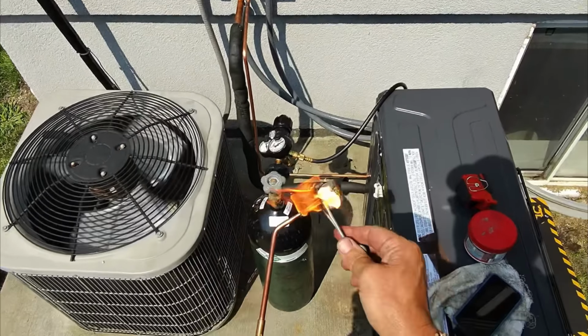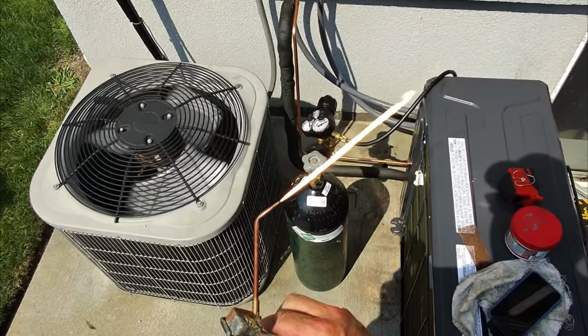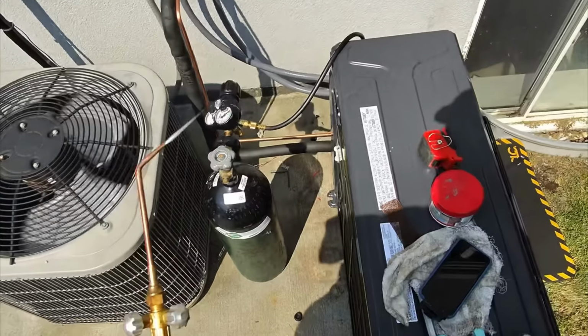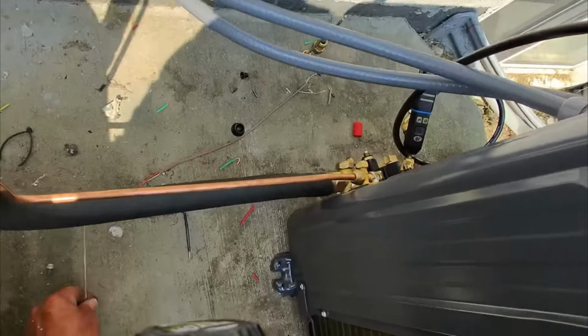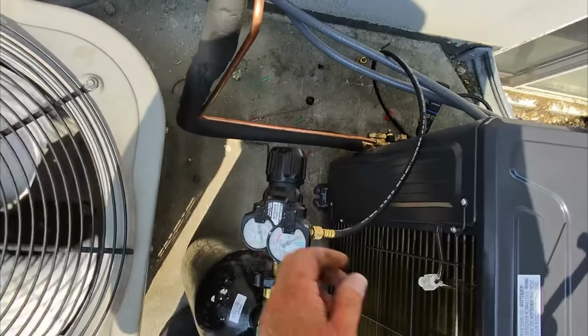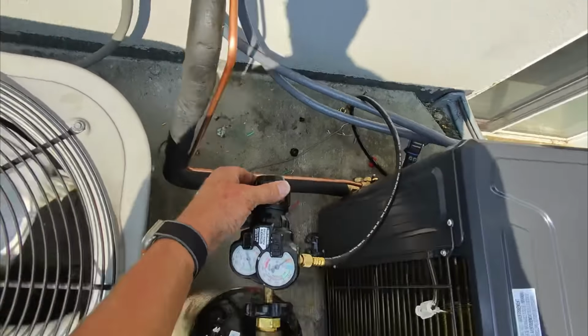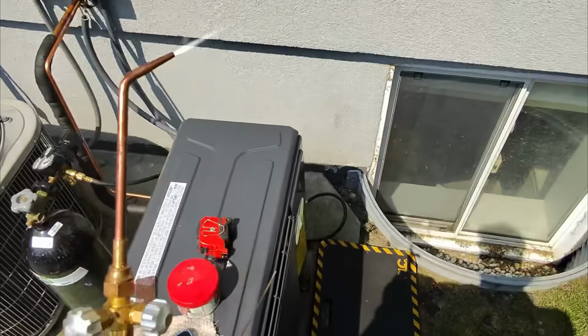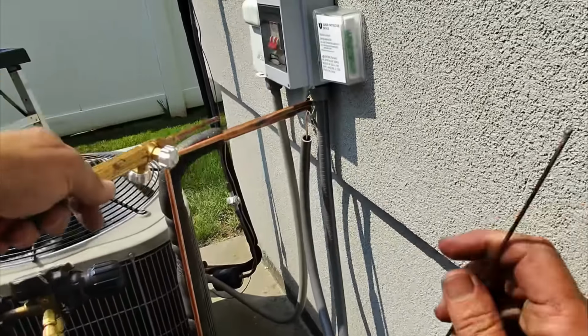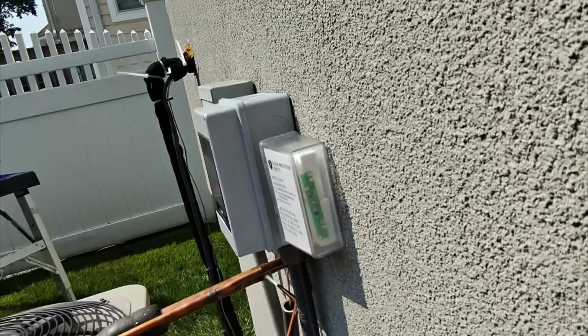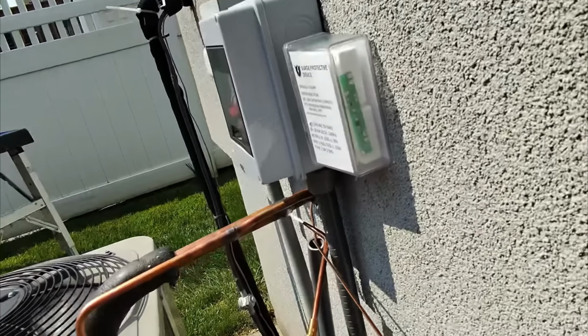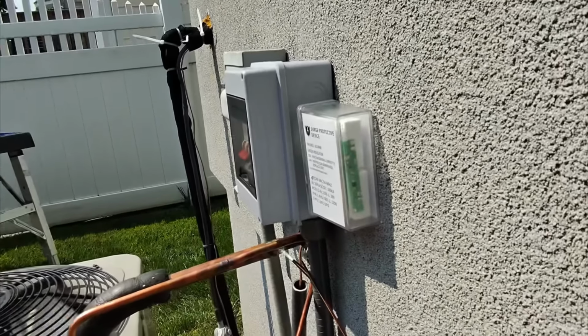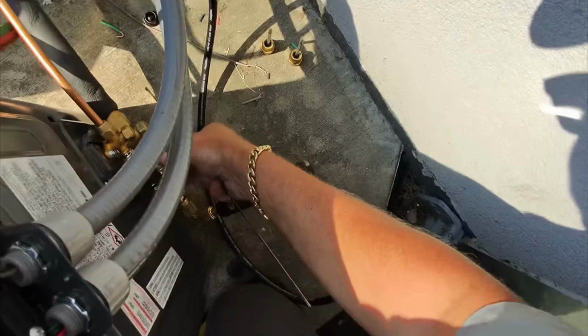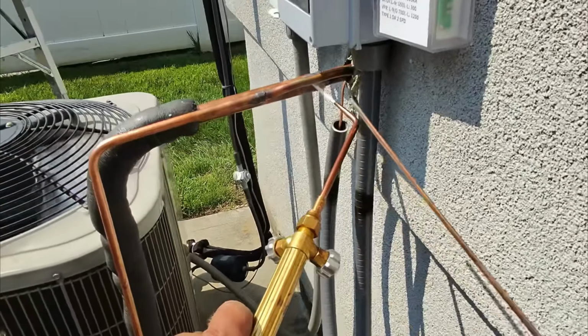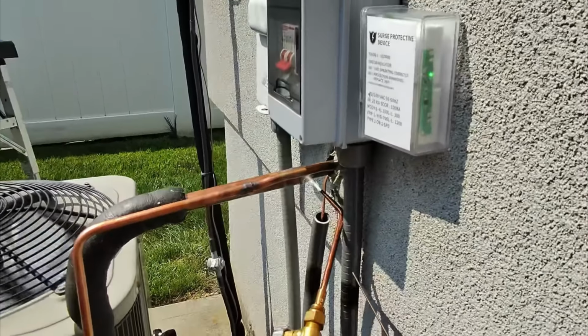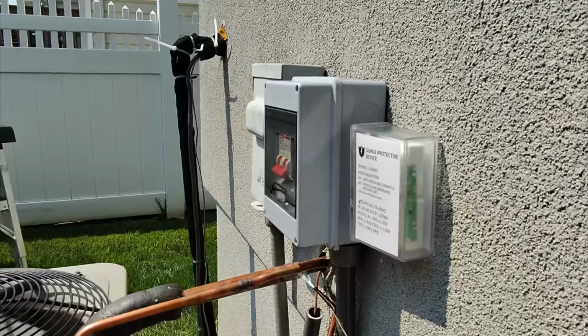Yep, I got a leak. Let's take care of that leak right now. I've got nitrogen set to braze. Let's see if I can get this without messing anything up right here. Let me open up the other side. Oh, see? Looked away for 1 second and I burnt the line set. Sucks.